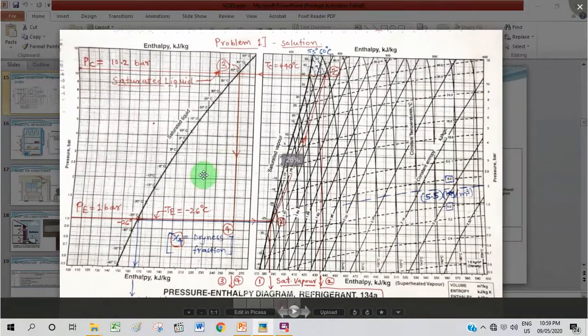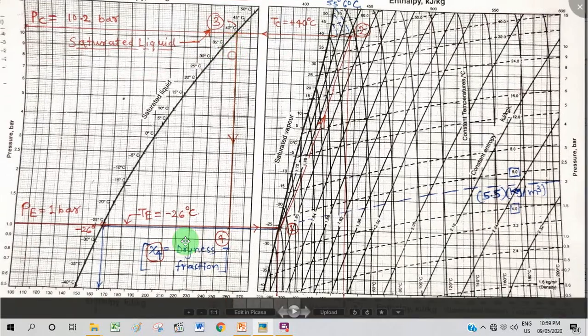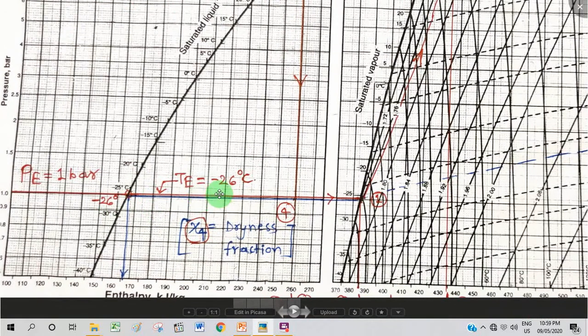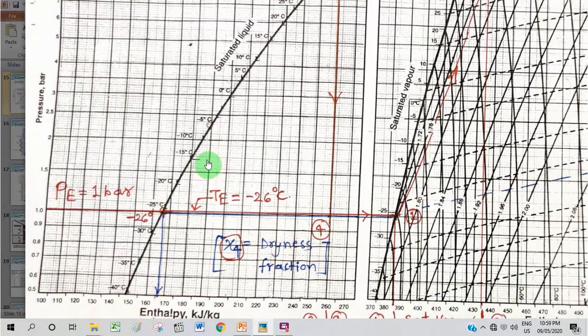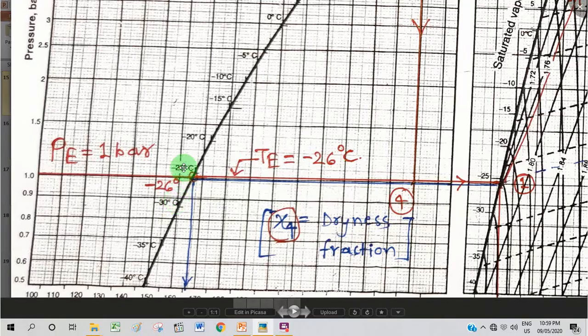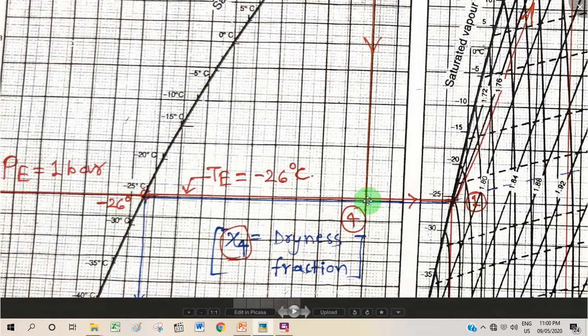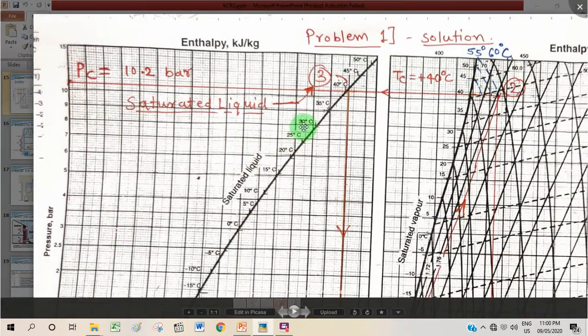We know two temperature limits: condensing and evaporating. The evaporating temperature is minus 26 degrees Celsius. We locate this on the saturated liquid curve — it falls between minus 25 and minus 30, so by approximation and judgment we mark the point just one degree below minus 25. Through this point we pass a horizontal constant-pressure line, which meets the pressure axis at approximately 1 bar, giving us the evaporating pressure. This line is extended to the saturated vapor curve.